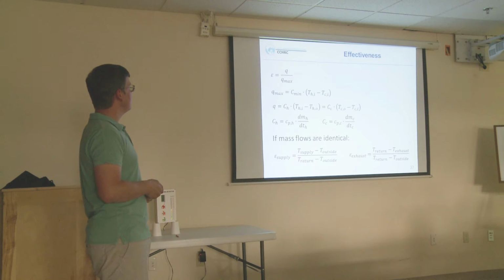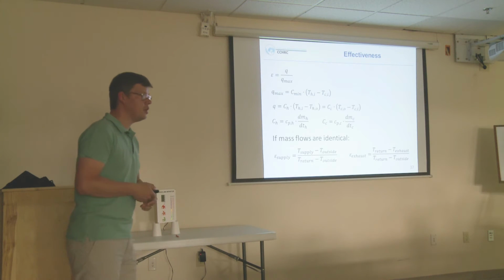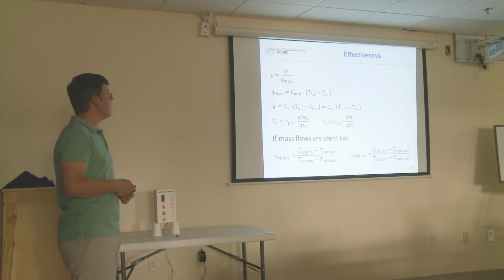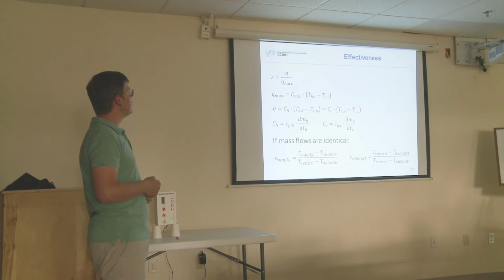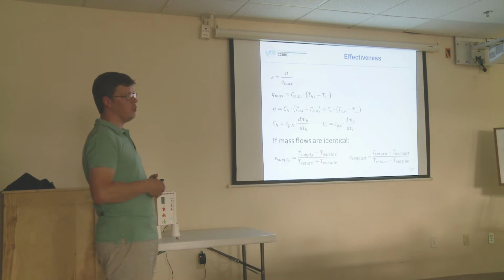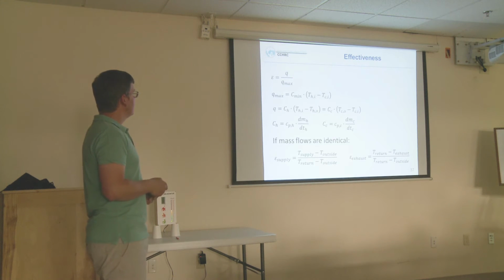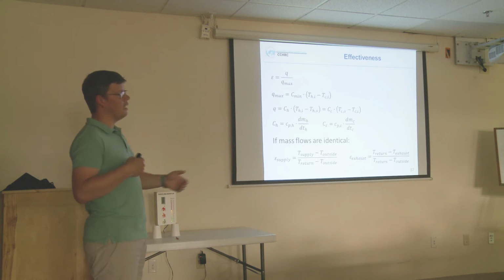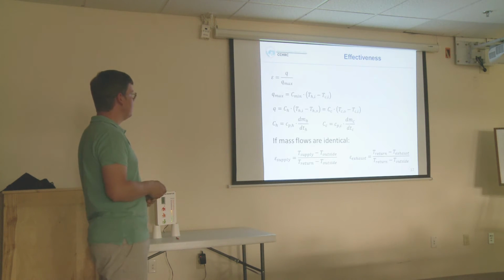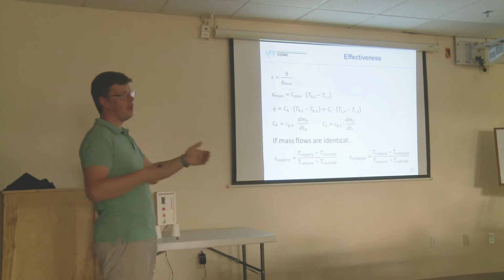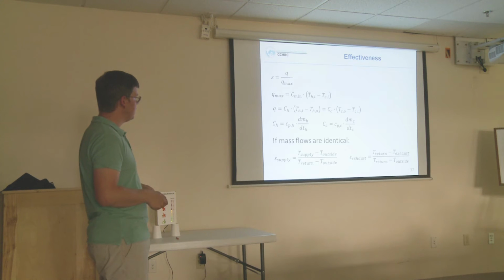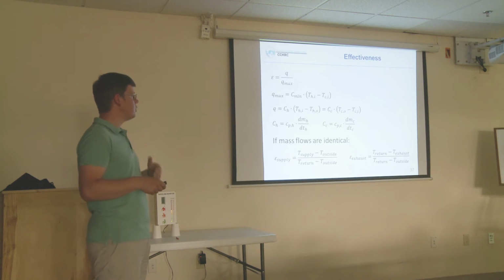Yeah, a little bit of math. When we talk about heat exchangers or heat recovery units, we always are interested in effectiveness. Effectiveness is just the amount of heat which is actually transferred over the maximum amount of heat which could be transferred. And this all goes to a very simple formula as long as the mass flow of the air is identical on the supply and exhaust side. So if we have the same speed of the fan and the same airflow in and out of the house, we can just use this simplified temperature formula to find out how warm or how cold our supply or exhaust air will be after it passes the heat exchanger.